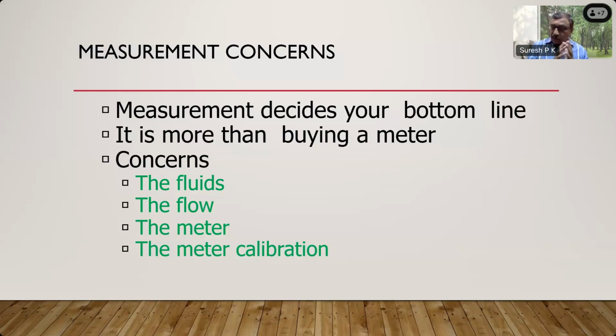So the meter has to be chosen carefully, because meters are costly. Say you take an orifice plate, which is a plate with a hole, and you have a DP transmitter, then you can measure the fluid flow. But that probably costs you less than 10,000 rupees. If you go for a mass flow meter of the same size, it will cost you lakhs. So it depends on the manufacturer. Whether you need to go for the highest accuracy meter for that particular application is your choice, or your industry's choice, whether it is worth doing that.